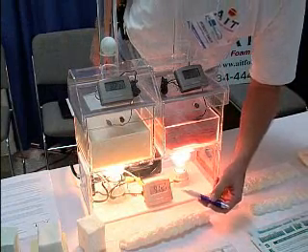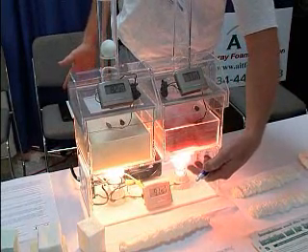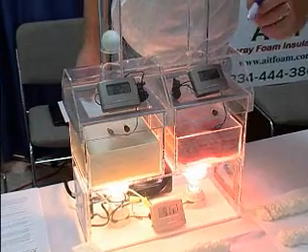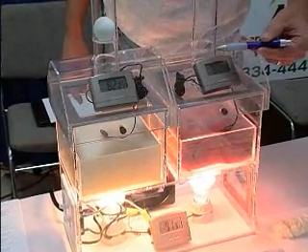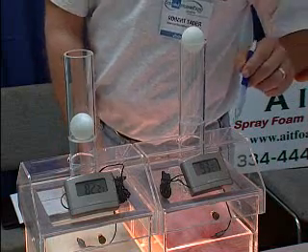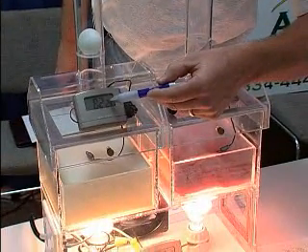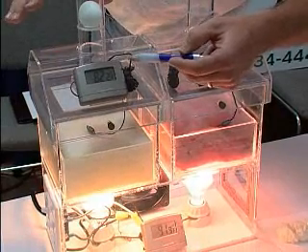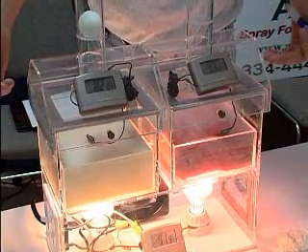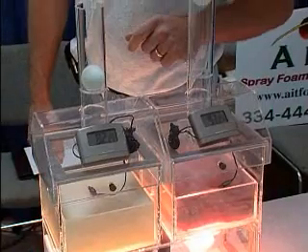These are standard light bulbs generating close to 92 degrees Fahrenheit, not too far from what an attic would be. With air movement, it brings almost all of that heat through — it's showing almost the full temperature measure coming through the fiberglass, which should be stopping that heat transfer. On the polyurethane foam side, it has lost about 10 degrees, closer to the ambient air temperature, as opposed to pushing that temperature through. Again, it comes back to the ability to stop air flow, which stops heat transfer. It also stops moisture movement, and this is the really telling sign.